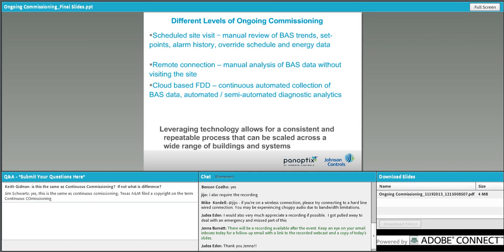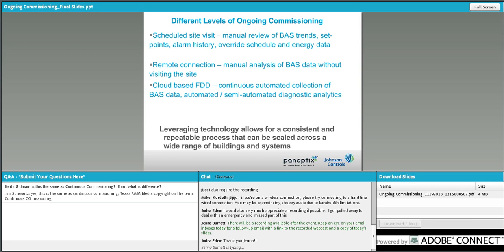The next level of ongoing commissioning typically includes some type of remote connection to the building through the BAS, such as a VPN connection to the building automation system. This type of connection allows an ongoing commissioning engineer to remotely access trends and data, saving time traveling to sites that may be distant. Often this data can be imported into other analysis tools to help identify potential faults and problem areas that require further investigation. Leveraging technology further is a cloud-based platform that provides FDD, fault detection and diagnostic capabilities.